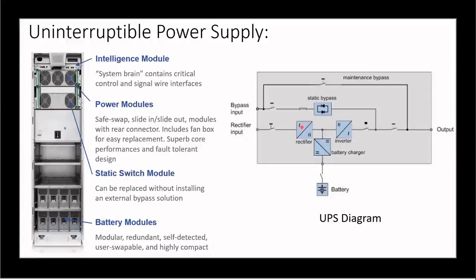Now, if something is wrong with the utility power, this static bypass will detect it. This is a switch, and if it detects anything wrong, then this breaker will be closed, and the battery will start supplying the load. So static bypass and maintenance bypass are two kinds of switch. The difference is this one is automatic. It will detect on its own and close or open automatically. While this maintenance bypass is not automatic, it's a manual switch.